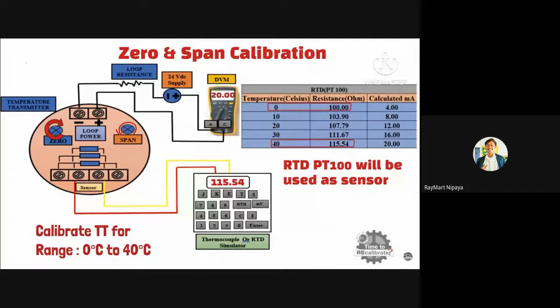For example, if the measured value is 20.10 milliamperes, then rotate the span screw in the counterclockwise direction until it becomes 20 milliamperes. Repeat this procedure a few times until you get exact values for zero calibration and span calibration. Once you are done with zero and span calibration, we need to perform a 5-point verification test to check the calibration.